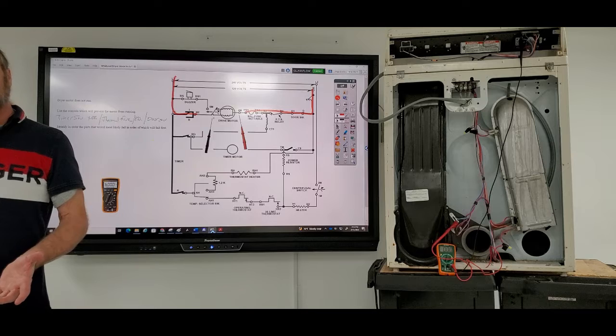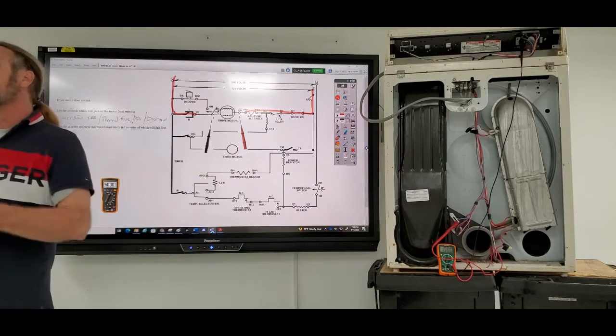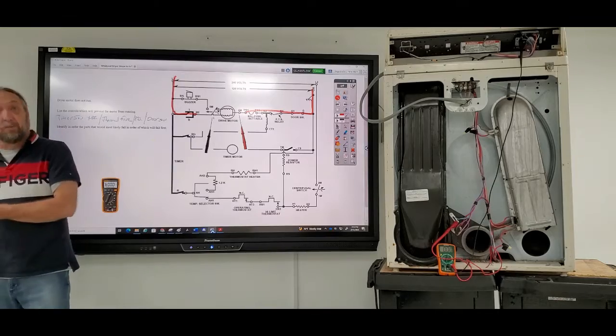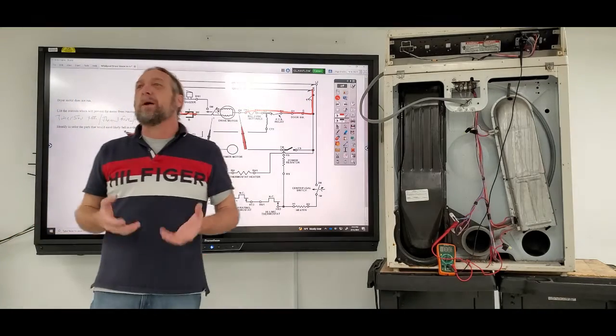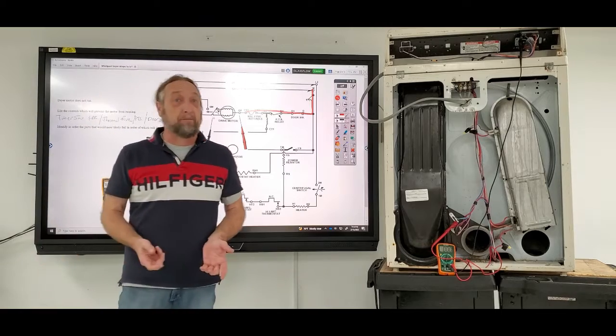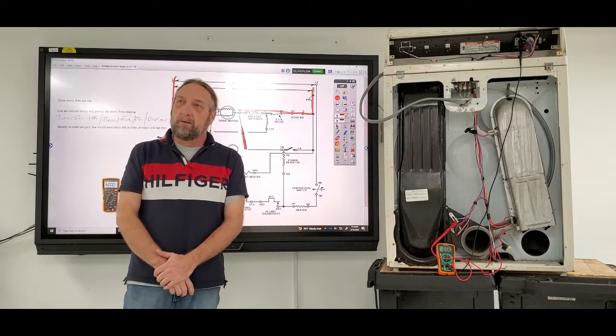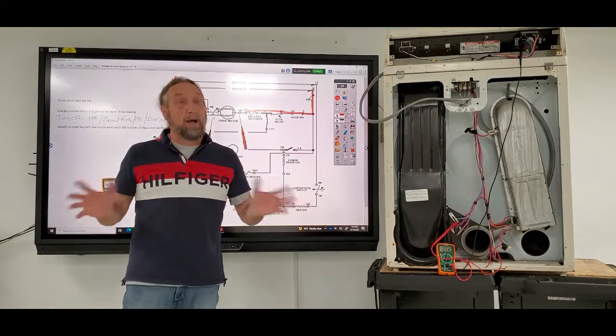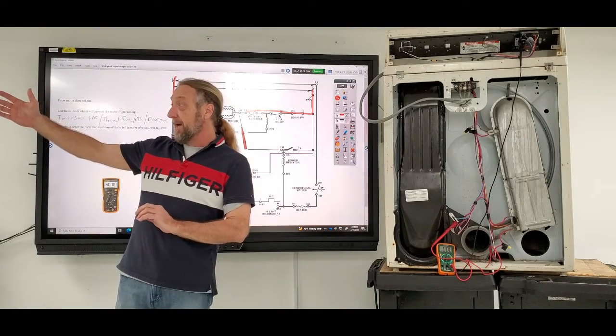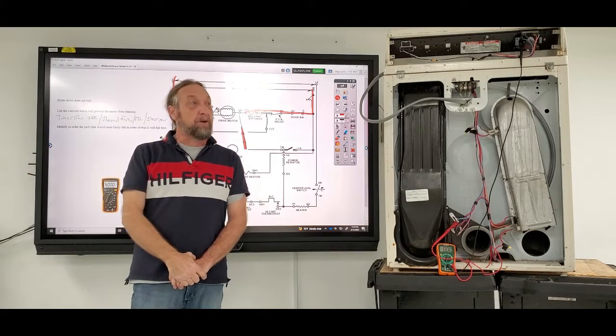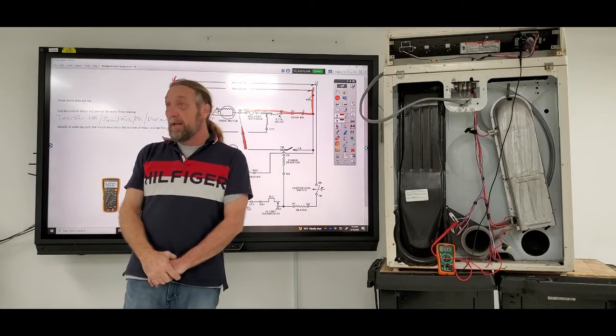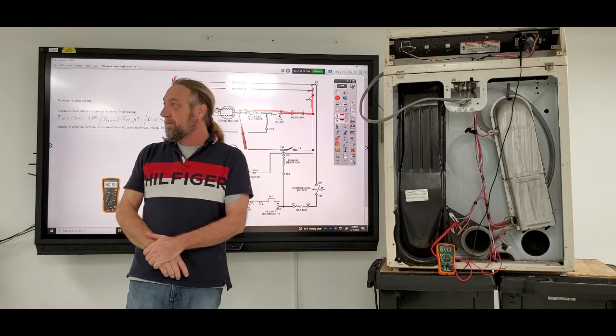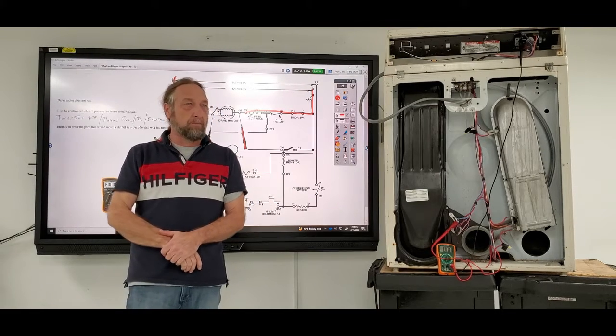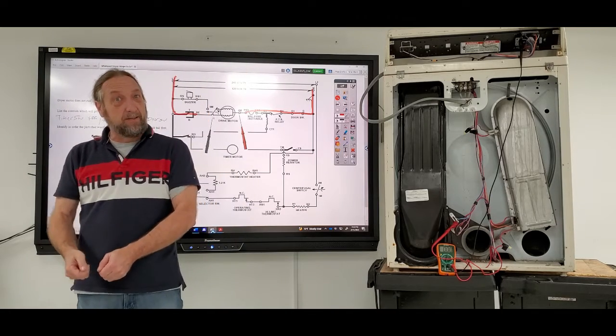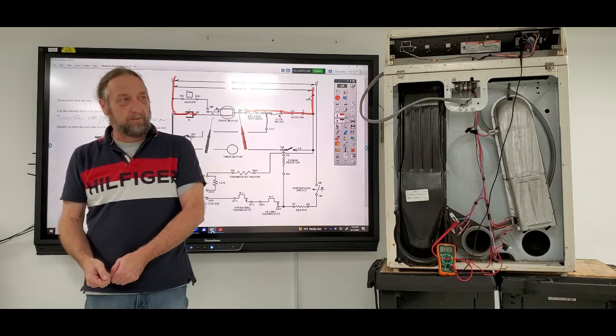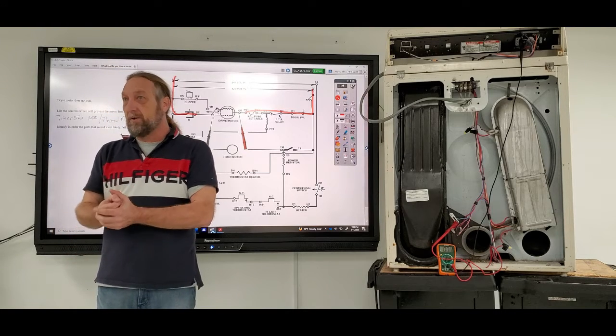Okay, so if you want to save yourself some time, spend an extra couple minutes confirming the problem that the guy diagnosed. Could you imagine someone saying a compressor's bad and you went and did a sealed system job, changing the compressor, an hour and a half later, put the compressor in and it's still not running? One, you spent an hour and a half of your time and you got a long day after that. Two, the customer's standing over, you've been in their house 2 hours, it's still not running, and you got to tell the customer, ma'am, I got to order a control board because the compressor's not working. Where you could have made a quick test and said, I'm not getting power to the compressor. So verify whatever a technician does.